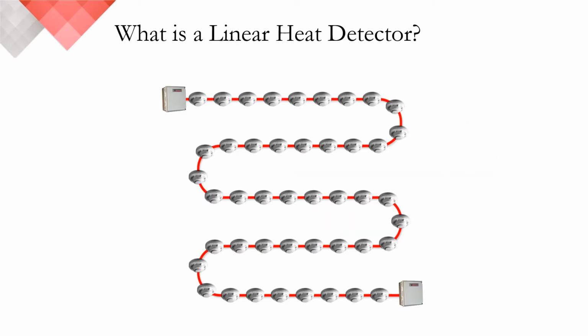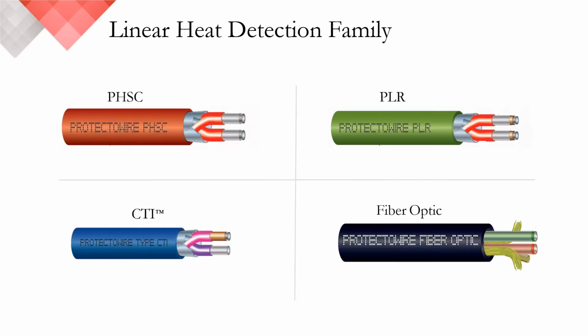Protectowire is best described as a continuous chain of spot heat detectors with the ability to sense heat or sudden increase in temperature anywhere along its length. A family of linear heat detection is available in several forms to meet a variety of challenges. To start, there's the PHSC series, which stands for Protectowire Heat Sensitive Cable. This is the product most widely used and the detector most relate to when they hear the name. Comprised of 2 steel conductors, the PHSC series can be integrated into any conventional or addressable system. However, there are limitations when considering equipment, which we'll get into in a few moments.